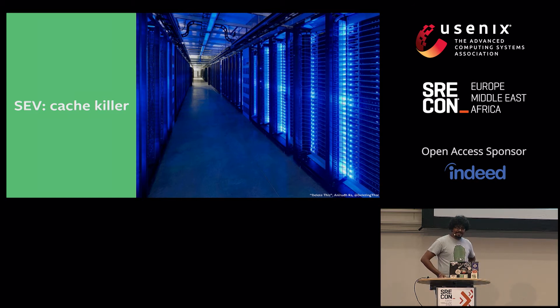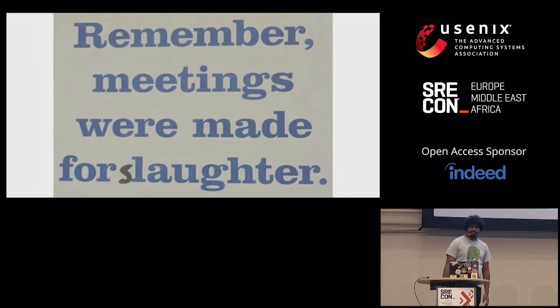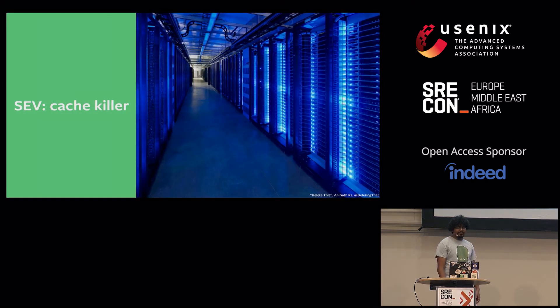The glue factory didn't check if machines had been drained — who sends machines there without draining them? — and it just quietly killed them. Production was not noticeably affected; we didn't have to go to Mark Zuckerberg and tell him we fucked up. The site didn't go down or even slow down, but we had taken live machines serving user traffic and slaughtered them. We ended up pushing migration handler writers to set retiring machines at the end of a job to a new state in the hardware management system called 'returned,' and made sure job schedulers would not run services on returned assets.